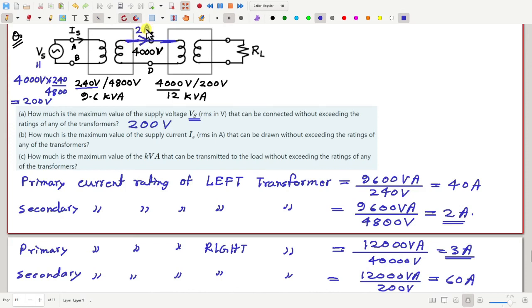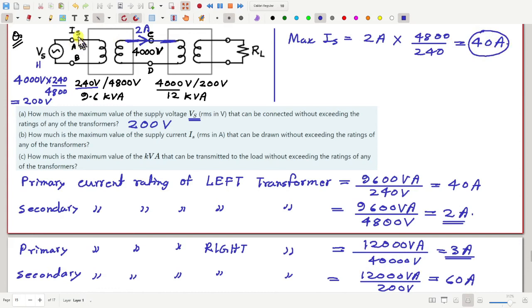Now if this current is 2 ampere, how much should be Is? Therefore the max value of Is should be equal to this 2 ampere multiplied by the ratio of the turns of this first transformer, which is 4800 by 240. This is the turns ratio of the first transformer. So this comes out to be 40 ampere. So then this is the answer. This is the maximum value of Is that we can allow without exceeding the current rating of any of these transformers. So the answer is 40 ampere for this second part.